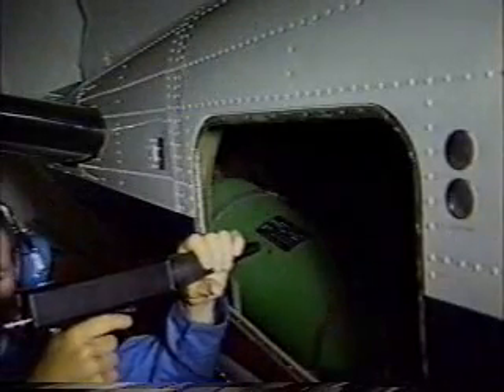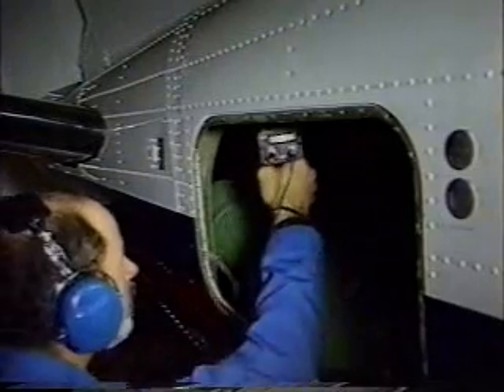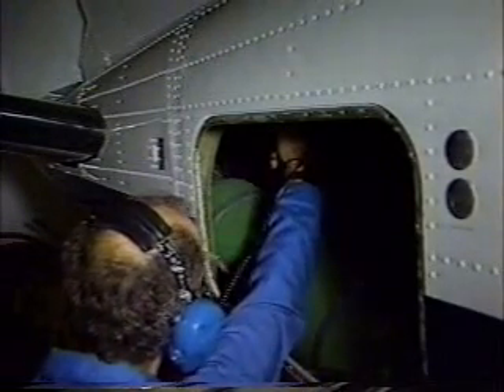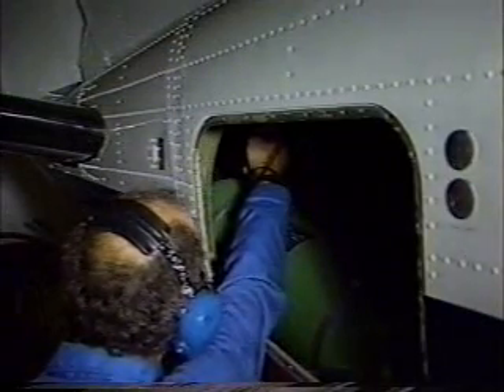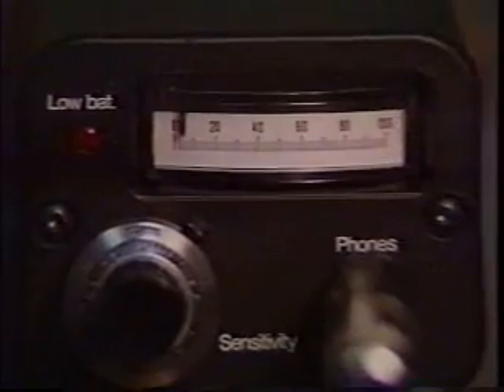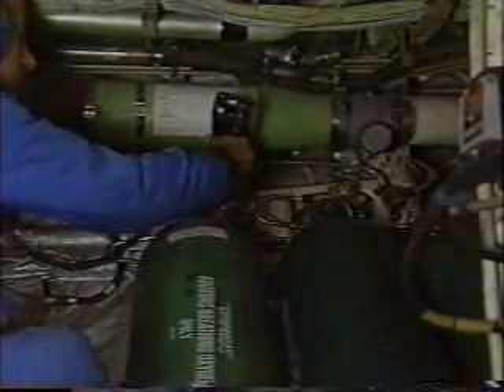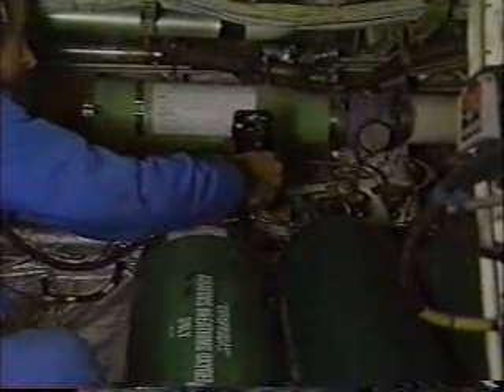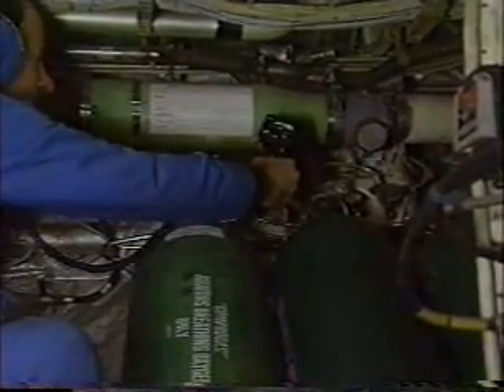Use the rubber probe, reduce the sensitivity, and listen. Watch the meter's response and confirm the leak site. If a noisy environment presents a problem, various shielding techniques can be used effectively to block out competing sounds. The rubber probe can be used to deflect the unwanted sounds. Or changing the angle of the ultraprobe may help.